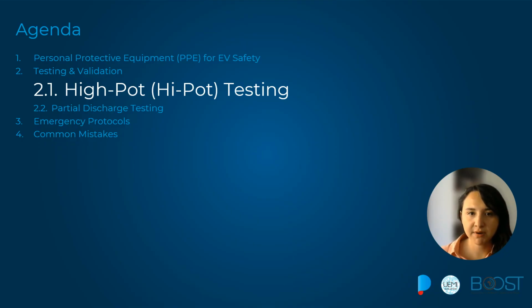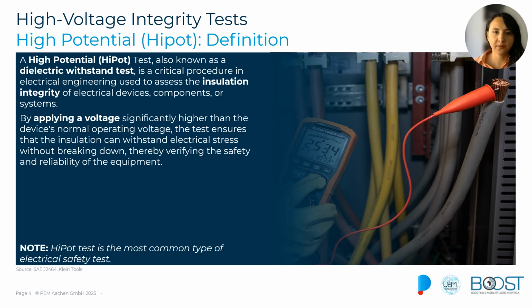The first one is the high-pot testing, and let's start by defining what it is. The high potential test, also known as the dielectric withstand test, measures whether the electrical component insulation can handle a voltage higher than the normal operating ratings or not. Essentially, during this testing, we deliberately stress the insulation and check if it breaks down or allows any dangerous leakage of current. We execute this testing because if the insulation lets higher voltage pass and has leakages, it is likely to fail in everyday operation, and we want to avoid that.